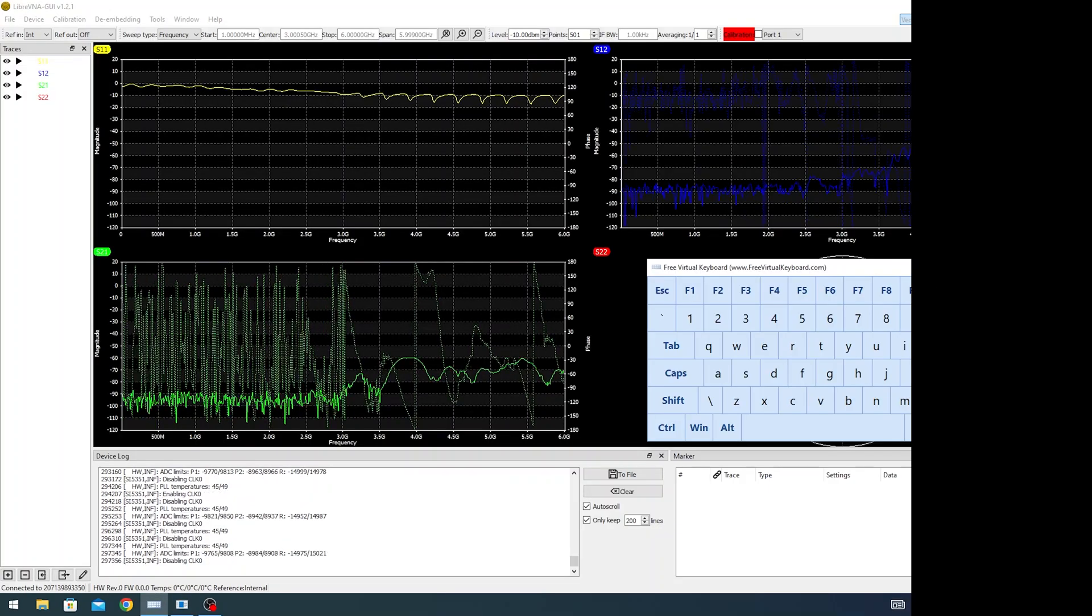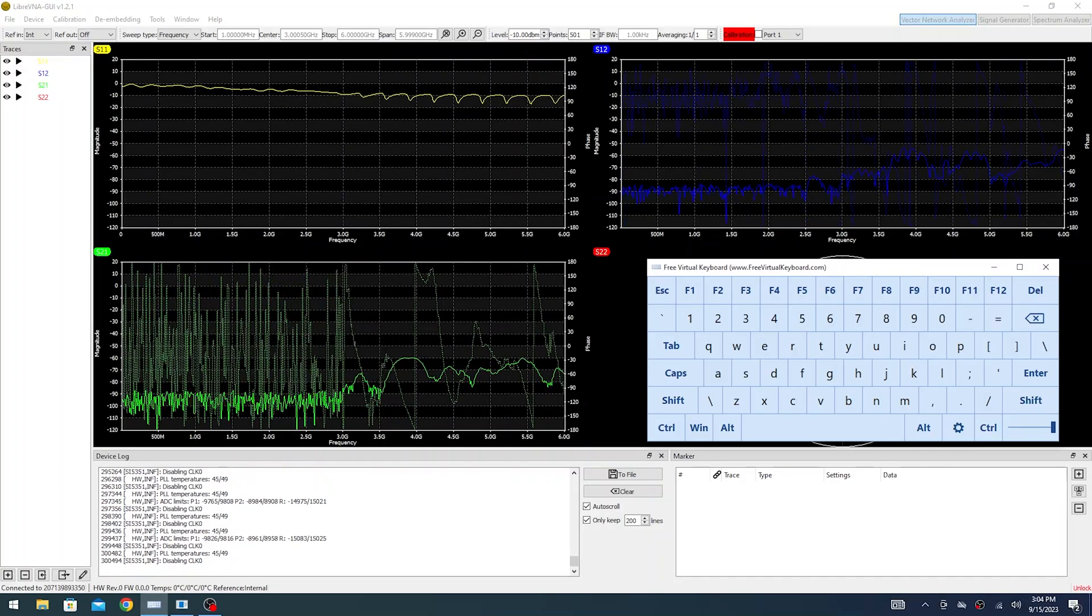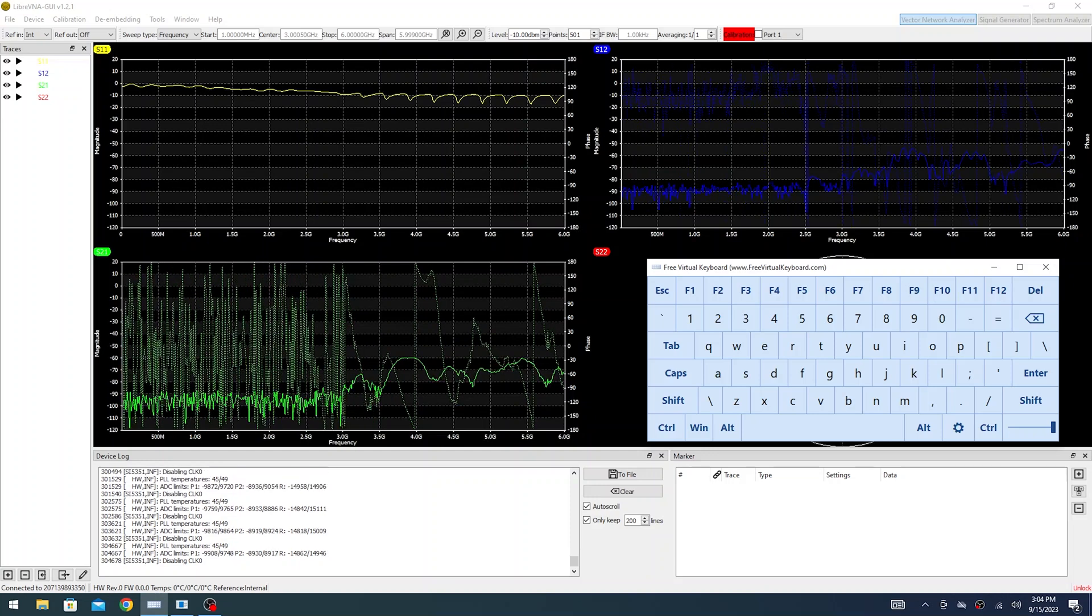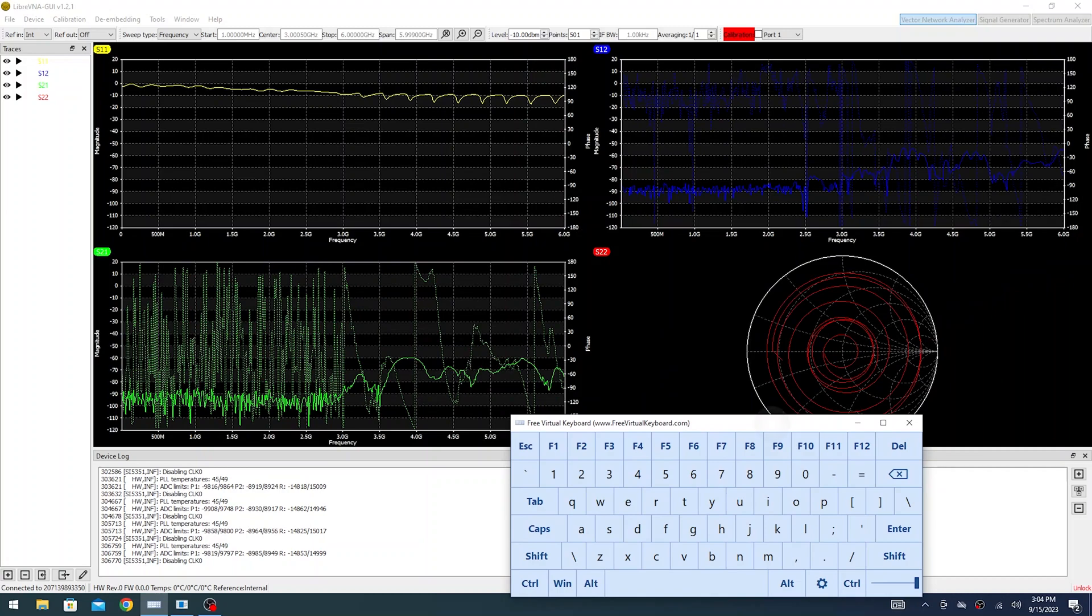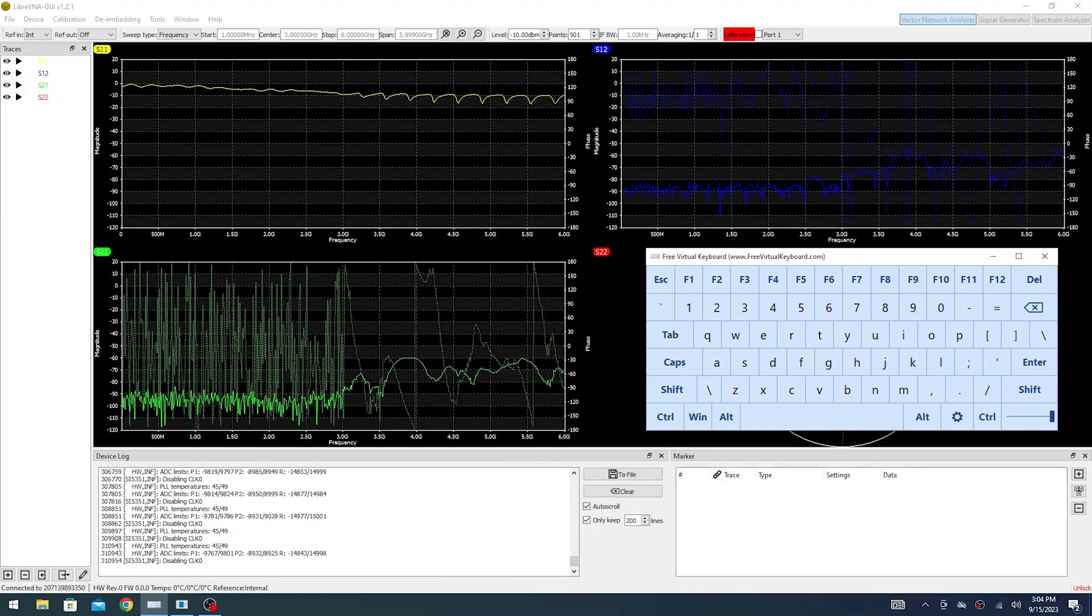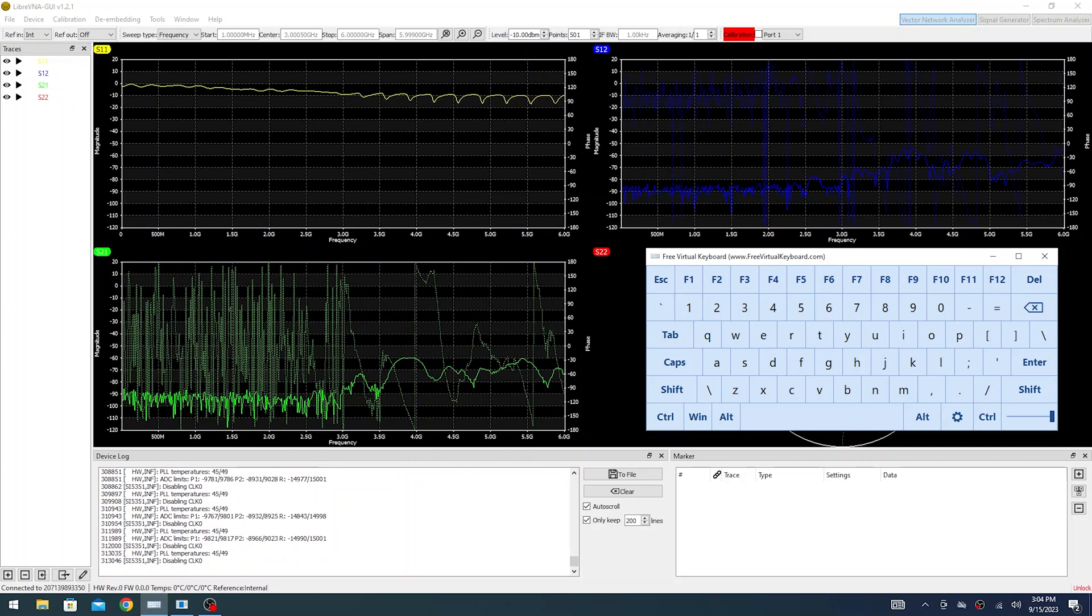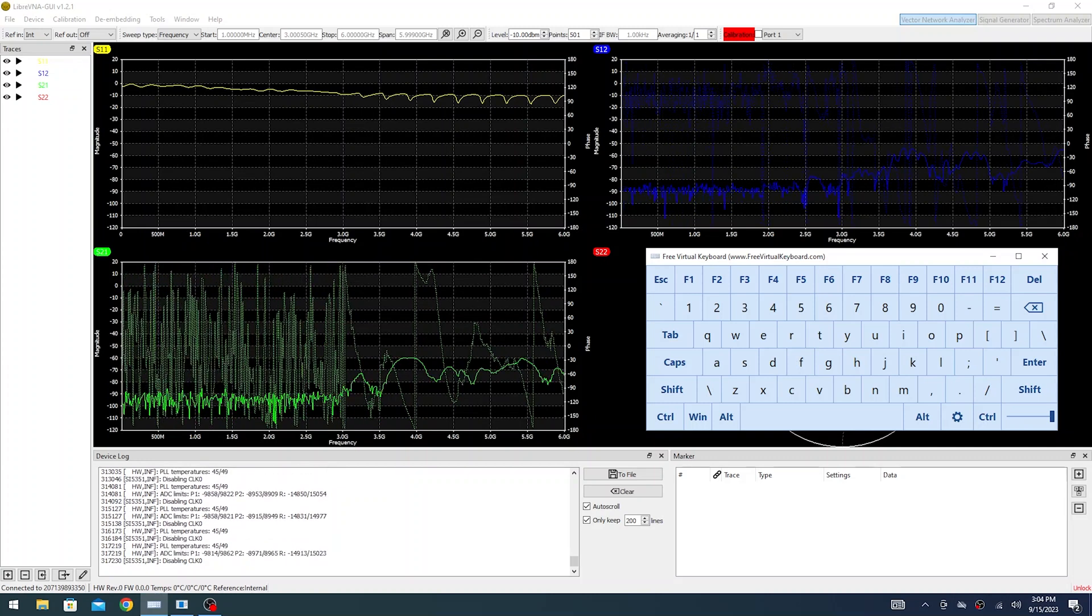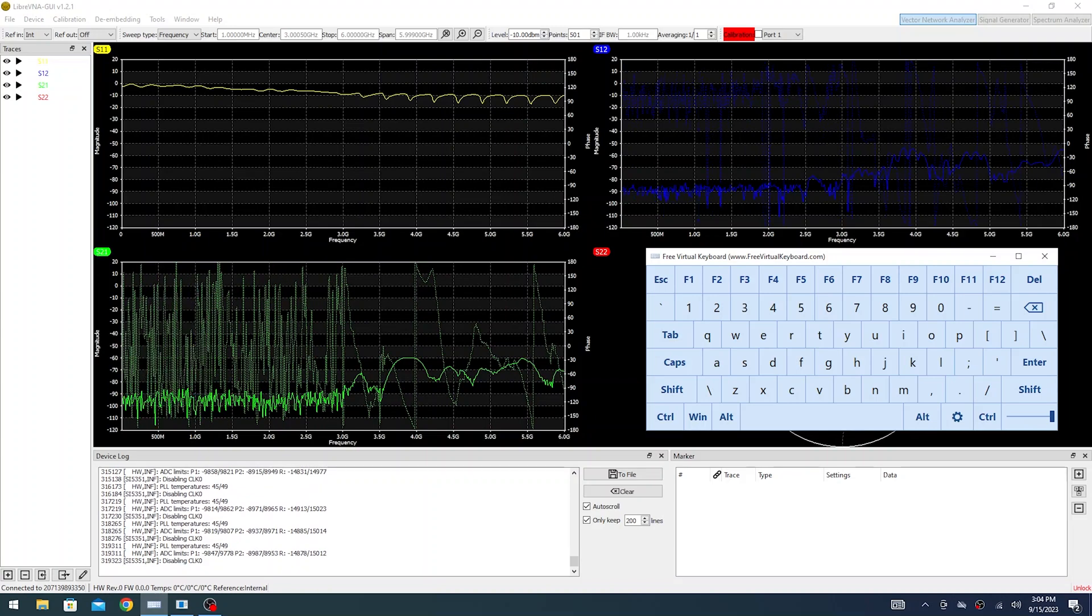So here I have the Libre VNA GUI brought up. We have all four S-parameters for a two-port network being plotted on screen. This also does a Smith chart for one of the ports if you want. Here, I'm not going to worry about that. I just want to focus on S11 and S21 right now. But of course, you could do all the stuff that we're doing here and plot this for S12 and S22.